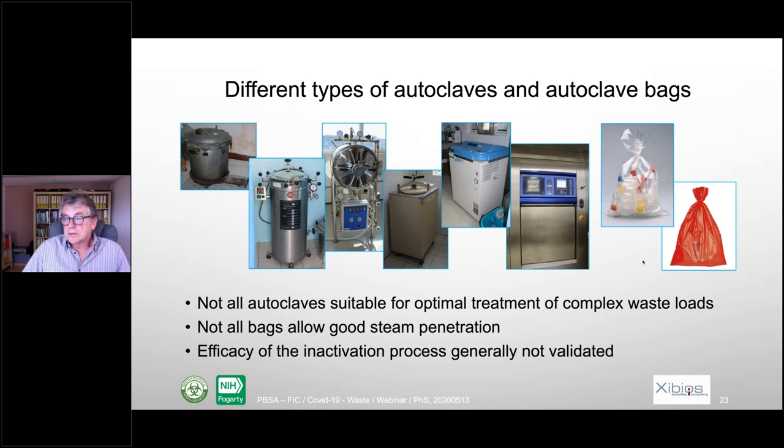If we look also at the bags, there are very different qualities of bags. Some bags really let the steam penetrate into the bags when they are at a high temperature, while some others don't allow the steam to penetrate. And so depending on the type of autoclave, the type of waste bag, the items which are inside, the size of the bags and so on, you might have very different results when you autoclave waste, for instance. So not all the autoclaves are suitable, and not all the bags are suitable. And so in some cases, autoclaving of waste does not produce good results.